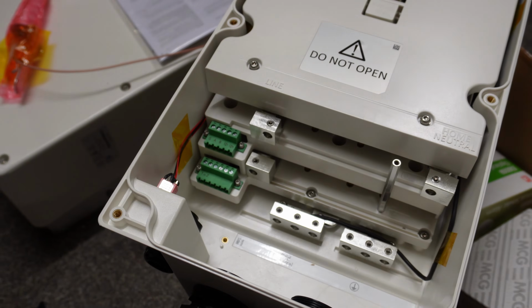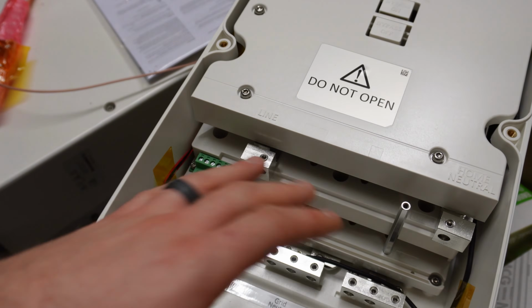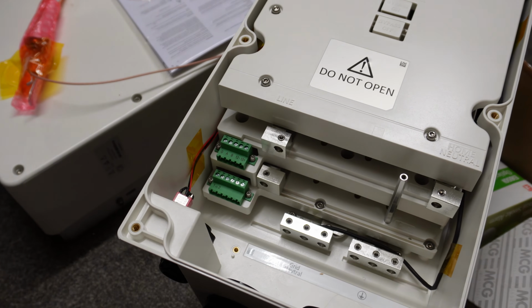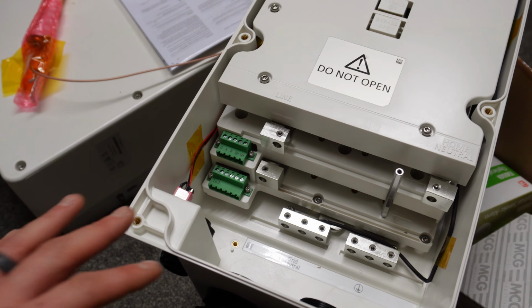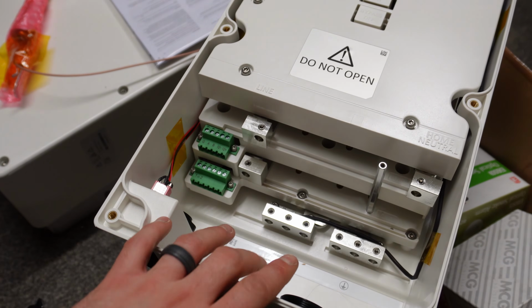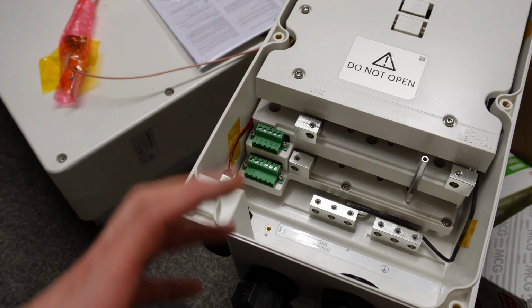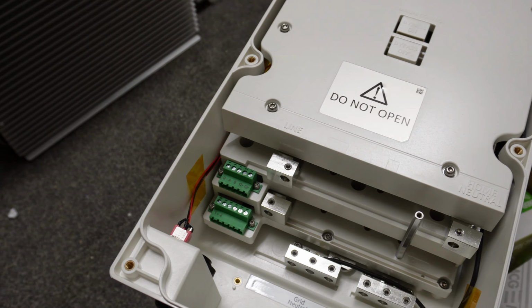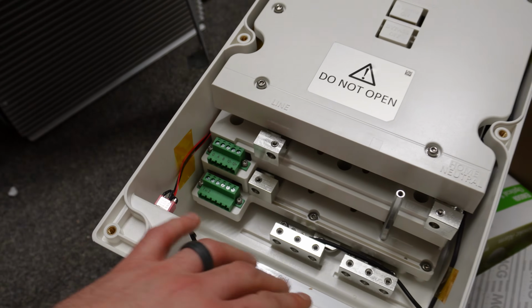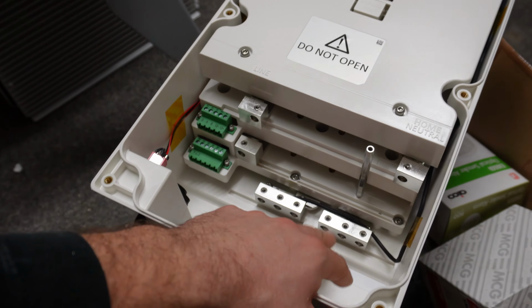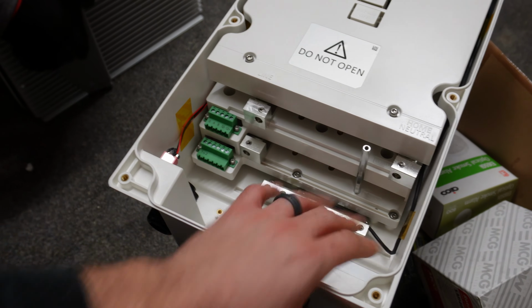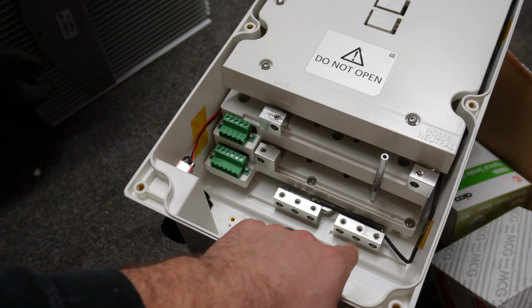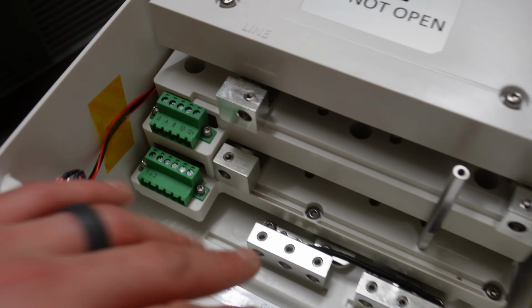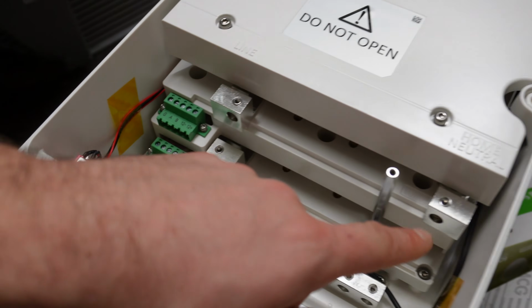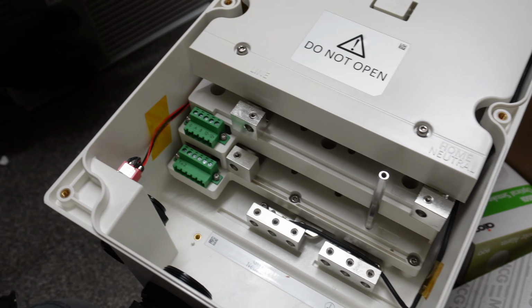So what that means is if the electricity board disconnected you intentionally, took away that neutral, and we didn't have this device, then you would lose your earthing arrangements as well. So that's called an open device or an open neutral. Hence why we put a parallel earth rod in. So the house does have its own earthing arrangements, so it still can be protected. In this device and in most devices that offer the off-grid, the neutrals are separated inside the device as well. So here we've got the grid neutral coming in, and then the load neutral to all of the properties.